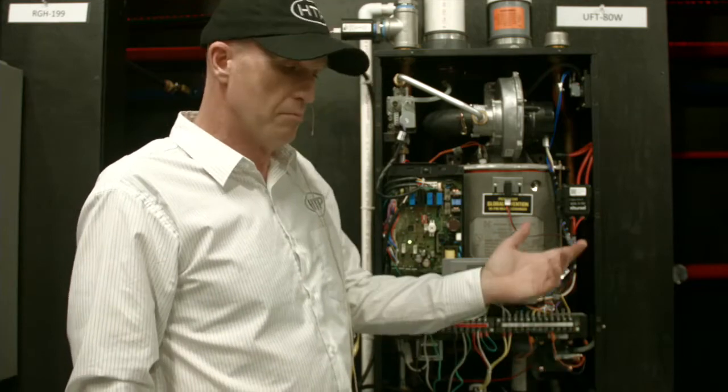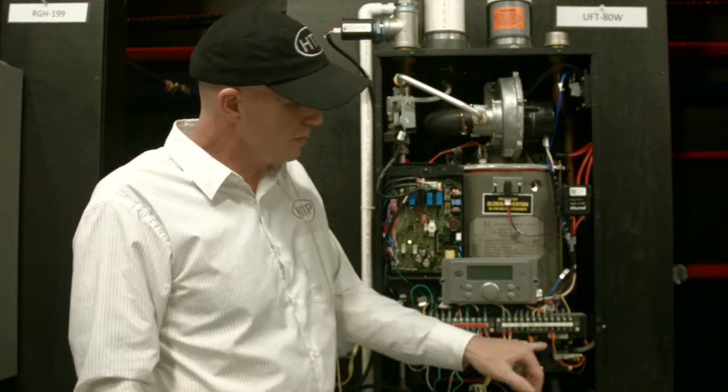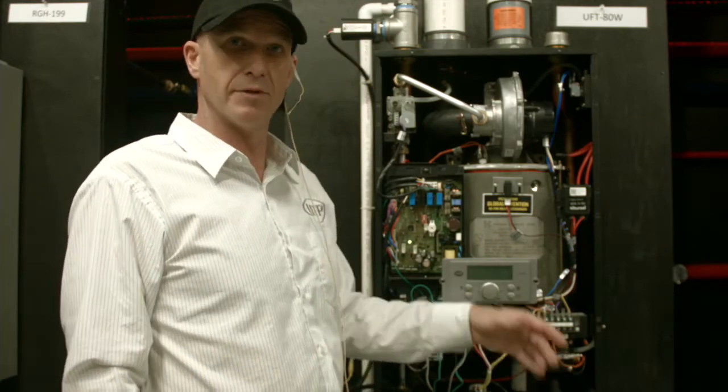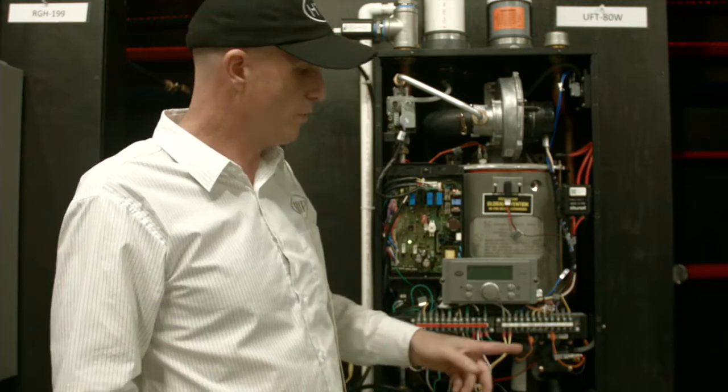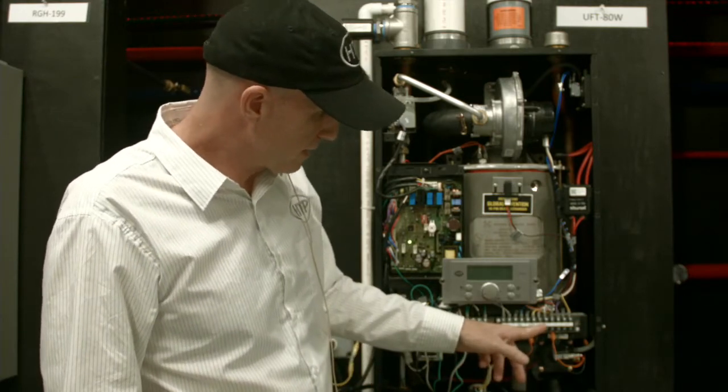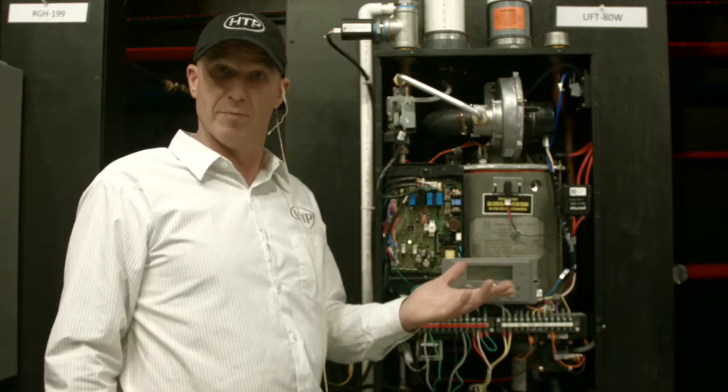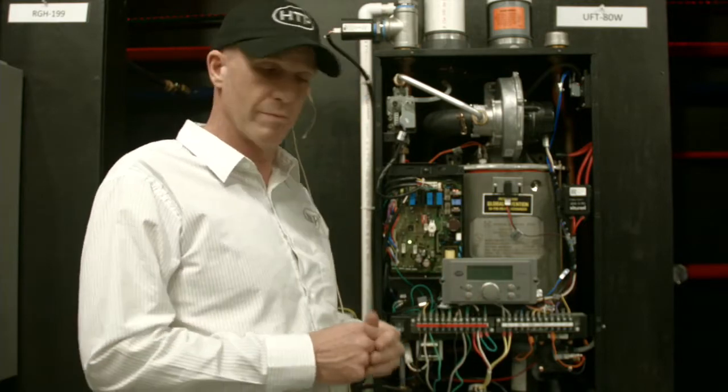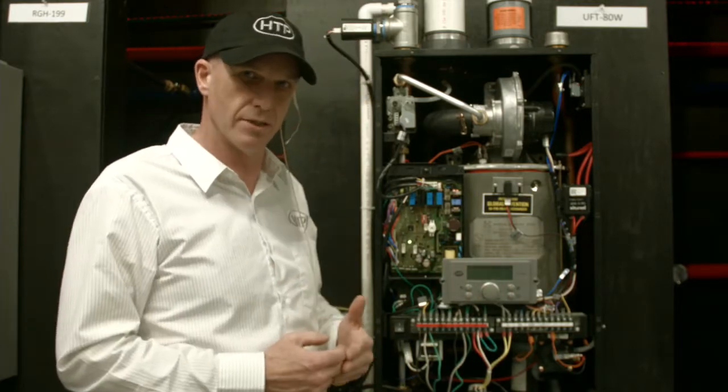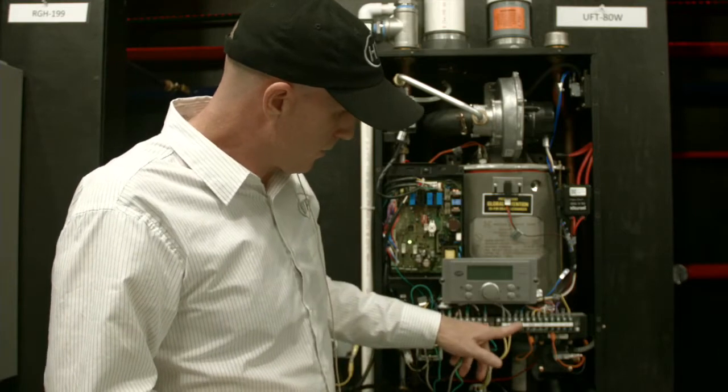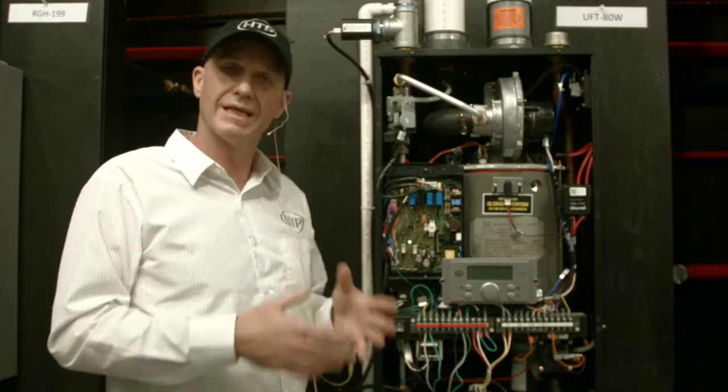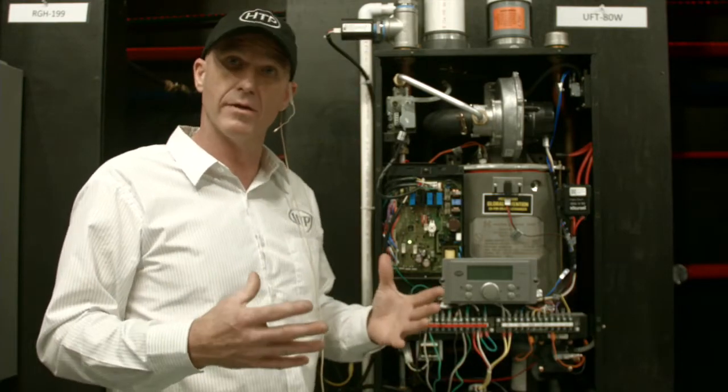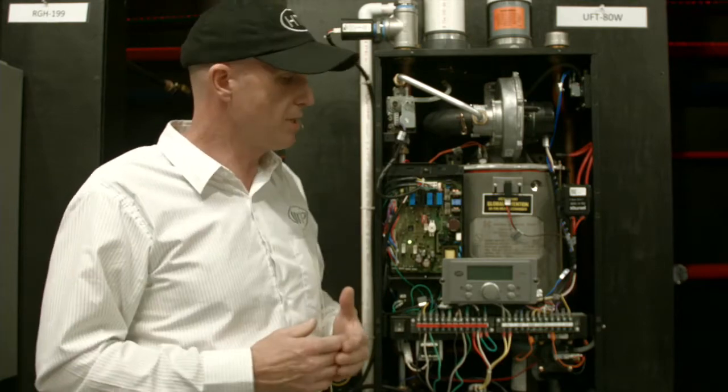We have our outdoor sensor that allows you to connect an outdoor sensor directly to the unit. Our thermostat input that would take a thermostat call or an end switch from a relay board. We have a direct zero to 10-volt input from a system. So if we have a building management system, we can send it a direct zero to 10-volt signal to it. It also has a place to put a system sensor. We can cascade, meaning we can put multiple units together, so it gives you a place to put the system sensor.